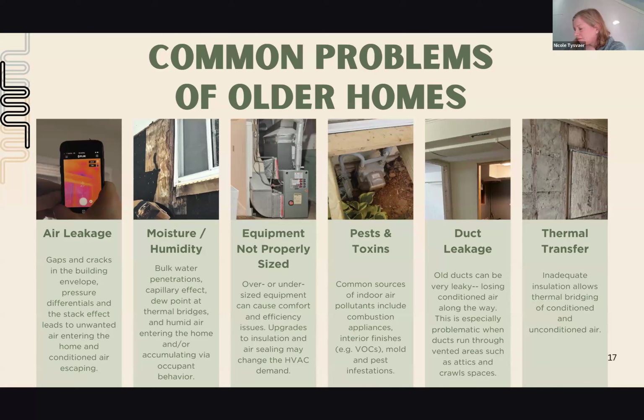Pests and toxins: again, that air sealing from the outside to the inside will keep your pests out, and any toxins on the exterior of the house, you want to keep from being sucked in by that stack effect. Duct leakage, you want to check that, and the AeroSeal will take care of that. And then the thermal transfer, mostly basements, but you want to make sure your envelope is insulated to the best it can be, especially crawl spaces. If your equipment's in a crawl space, you want to insulate the exterior walls of the crawl space, or the main floor of the house there.